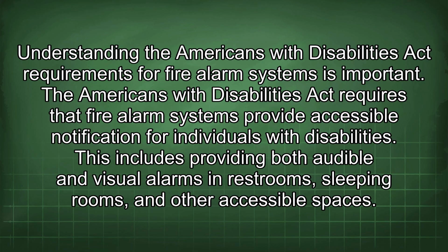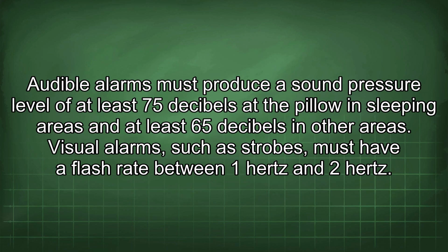Understanding the Americans with Disabilities Act requirements for fire alarm systems is important. The Americans with Disabilities Act requires that fire alarm systems provide accessible notification for individuals with disabilities. This includes providing both audible and visual alarms in restrooms, sleeping rooms, and other accessible spaces. Audible alarms must produce a sound pressure level of at least 75 decibels at the pillow in sleeping areas and at least 65 decibels in other areas. Visual alarms, such as strobes, must have a flash rate between 1 Hz and 2 Hz.